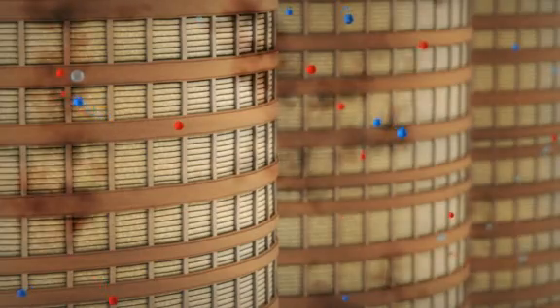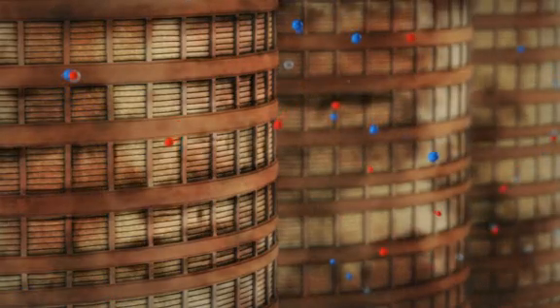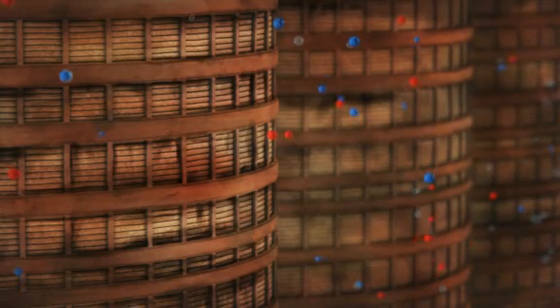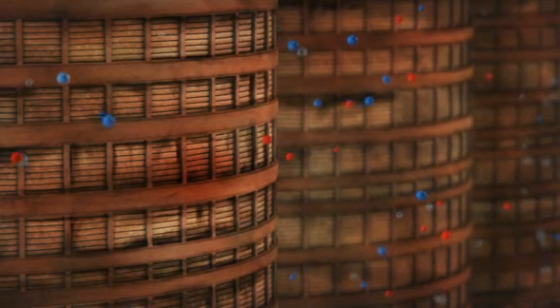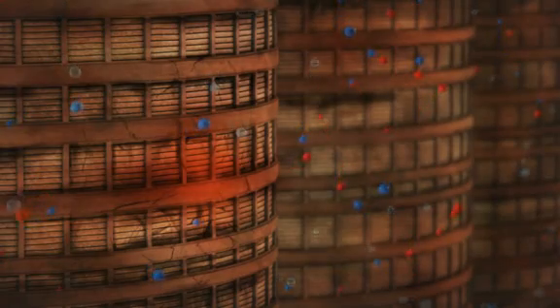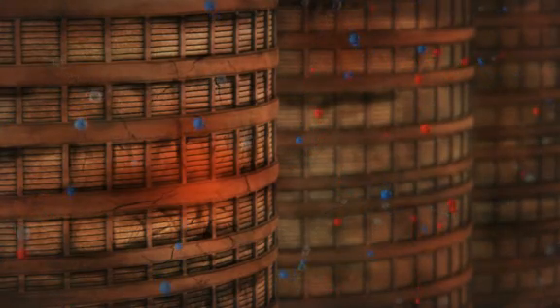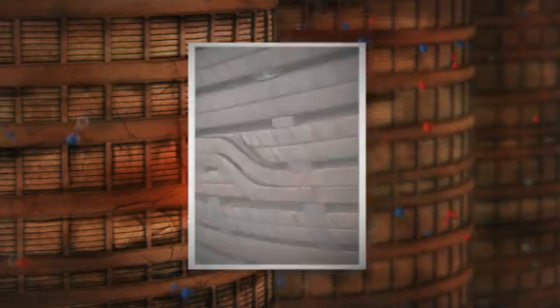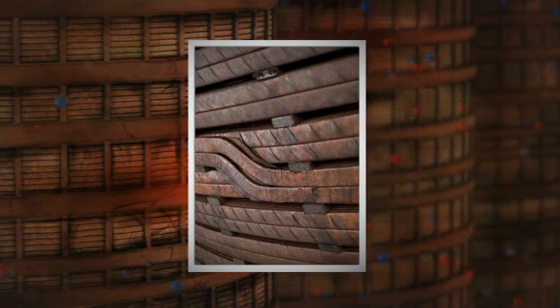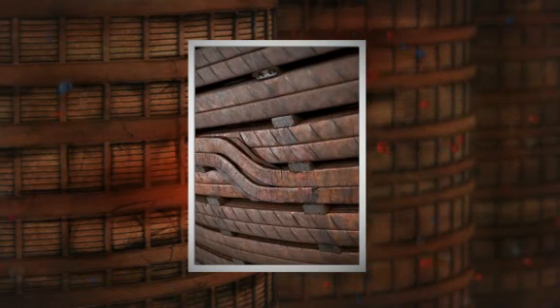Additionally, deposits and sludge form on the surface of the transformer windings. This reduces the heat transfer capability and therefore the cooling capability of the oil. The decomposition products also attack the paper insulation of the transformer windings, and the paper loses its mechanical and dielectric properties. The process finally results in defective spots in the insulation.